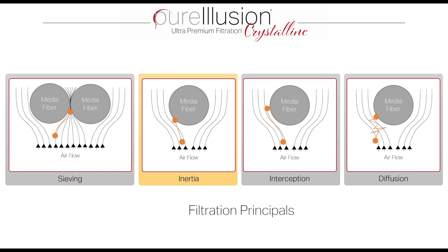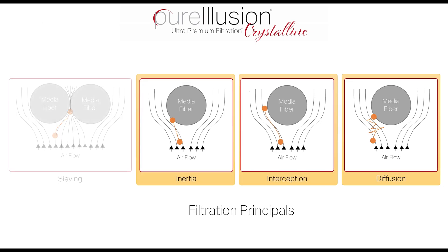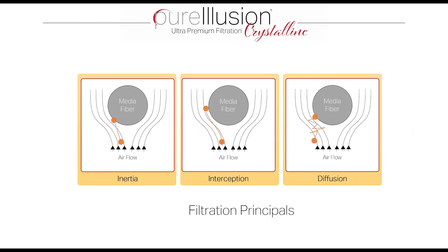Rather, we use inertial impact, interception, and diffusion principles. Inertial impact occurs when a particle is of sufficient size that it is able to break through the airflow carrying it around a media fiber and impact the media fiber itself. So inertial impact occurs when a particle carries enough inertia to impact the media fiber even though the air is flowing around it.